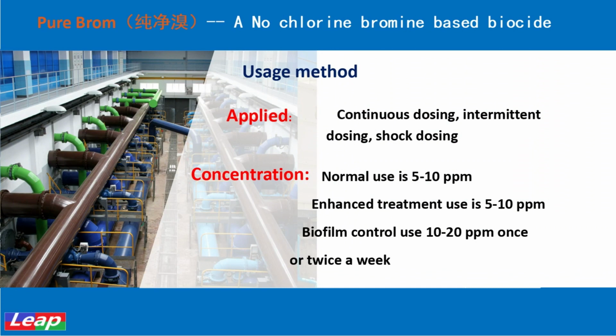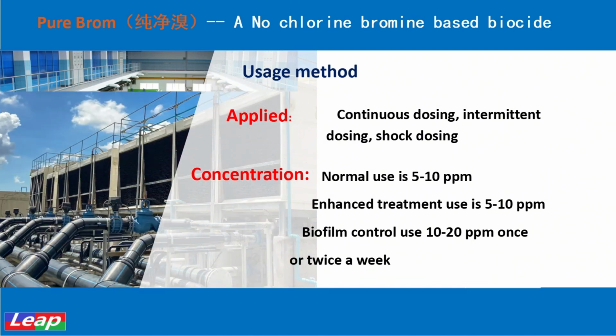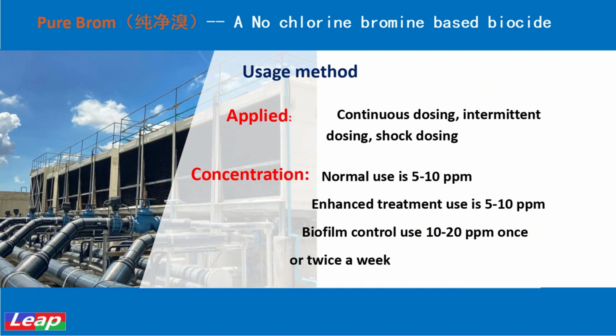For cooling tower treatment, Pure Brom can be used alone or in combination with other oxidizing biocides and non-oxidizing biocides. When used in conjunction with other effective biocides, shock dosing Pure Brom at a dosage of 10 to 20 ppm once or twice a week can effectively control planktonic microorganisms and biofilm in the cooling tower.